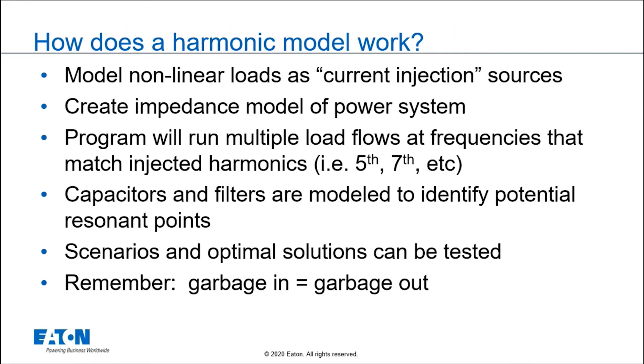Now that we've established that we want to look at our existing system or new construction system and figure out if we have a harmonics issue, how does that harmonic model work? Basically, we're going to model those nonlinear loads as current injection sources — harmonics come from the load. We're going to create an impedance model of the system and model that system at multiple different frequencies based on what the load currents tell us. So we're going to model a fifth harmonic impedance network, a seventh harmonic impedance network, and a 60 Hz impedance network — all of those impedance networks are going to be important, and that's all done through the software.